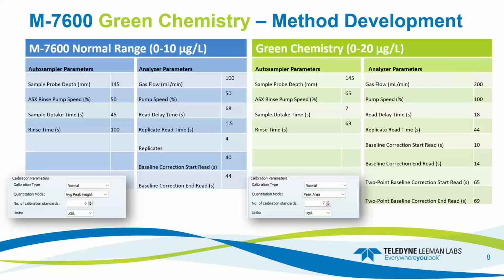To shorten that analysis, I changed 3 variables that affect the residence time in the system. So the sample uptake time was shortened, so there's less sample going in, while the gas flow and the pump speed were increased. So this was to push the sample through quickly. So this makes less sample travel faster through the system.